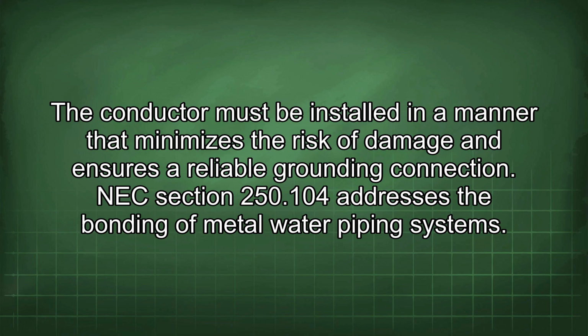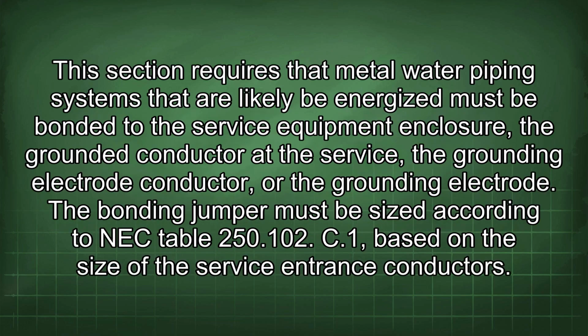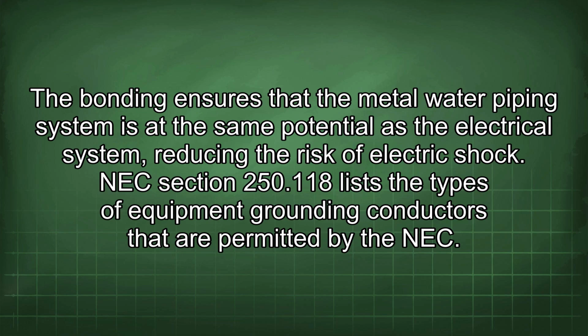NEC section 250.104 addresses the bonding of metal water piping systems. This section requires that metal water piping systems that are likely to be energized must be bonded to the service equipment enclosure, the grounded conductor at the service, the grounding electrode conductor, or the grounding electrode. The bonding jumper must be sized according to NEC Table 250.102(C)(1) based on the size of the service entrance conductors. The bonding ensures that the metal water piping system is at the same potential as the electrical system, reducing the risk of electric shock.